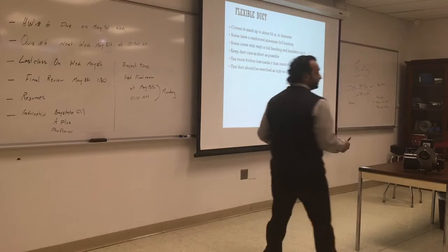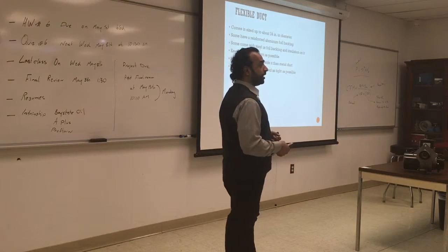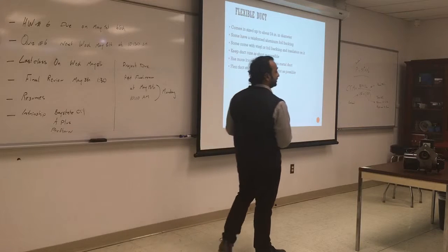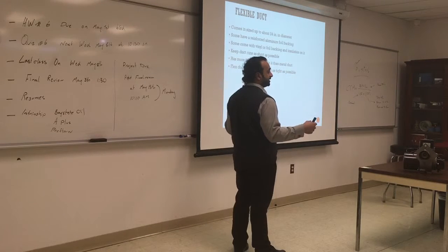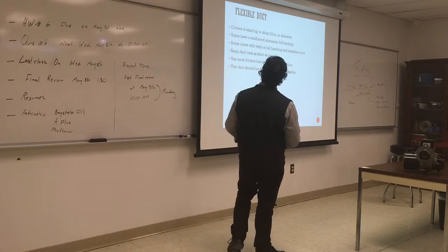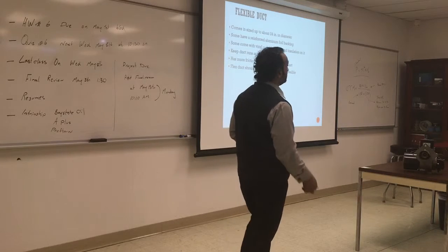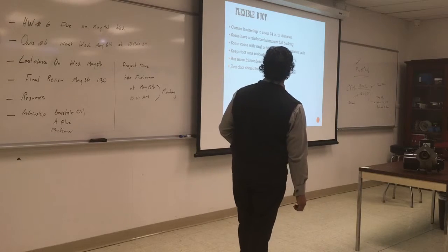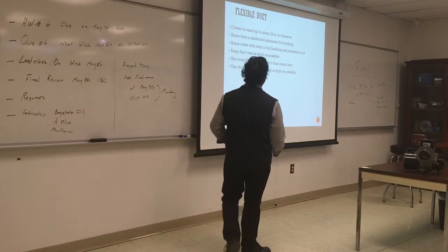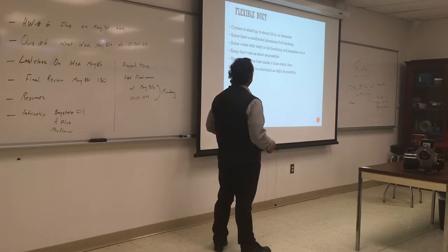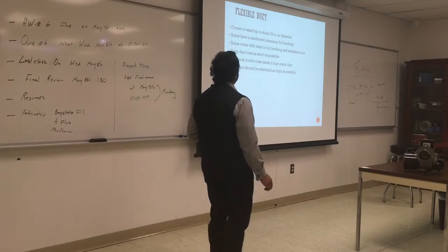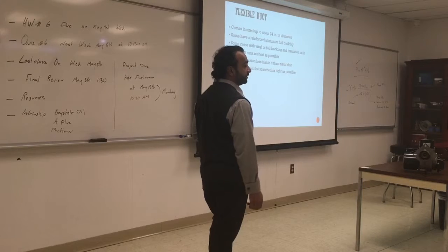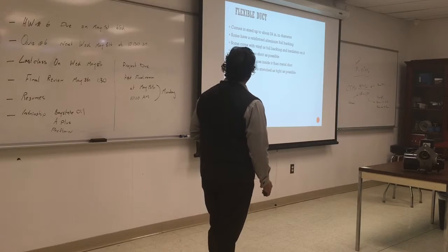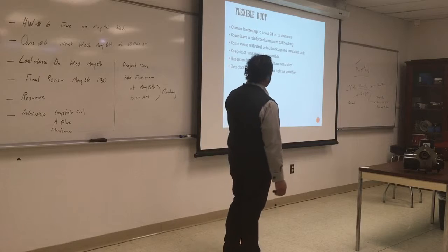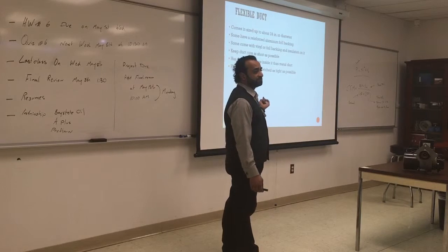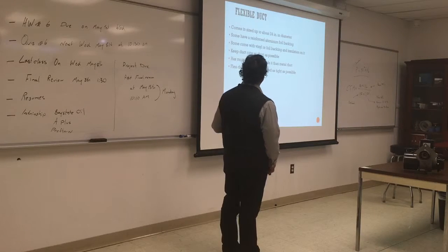Flexible duct, these are the ones that come with the support, with the wire, and you have to make sure that you don't overexpand them, and put them at the right distance. They come up to 24 inches in diameter. Some have reinforced aluminum foil backing to keep it in place. Some come with vinyl foil backing or insulation on it. Keep duct runs as short as possible. We said 6 to 10 feet is the maximum. You don't want more than that.